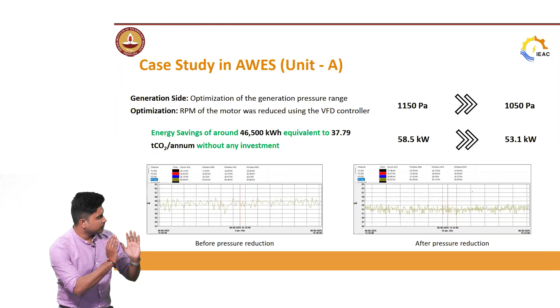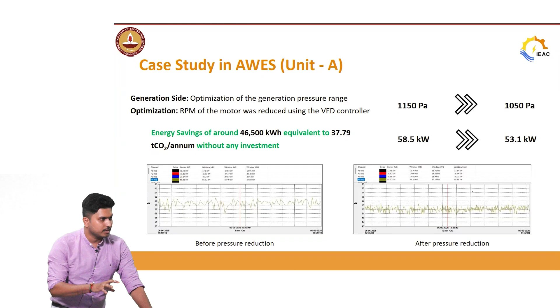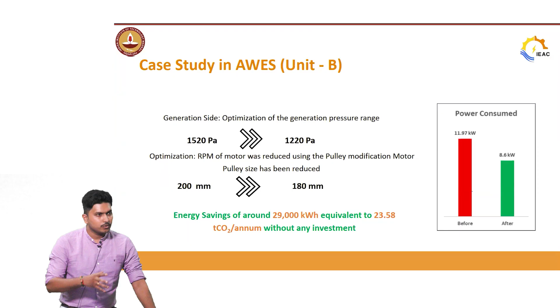So instead of using VFDs, where you need to invest for the motor, you need to buy a VFD, you need to install a VFD, you need to wire it, you have one more option: you can change the pulley diameter of the motor. The torque required is only around 10 Newton meter, and you will be producing only 10 Newton meter. Based on that, you will add a pulley for that. When you do that, your power consumption, which is around 12 kilowatts (11.97), comes down to around 8.5 kilowatts just by changing the pulley of your motor.